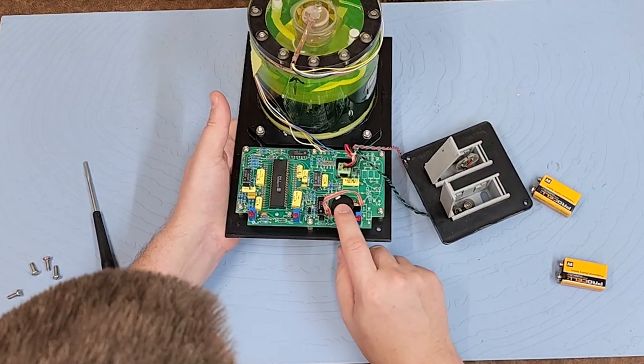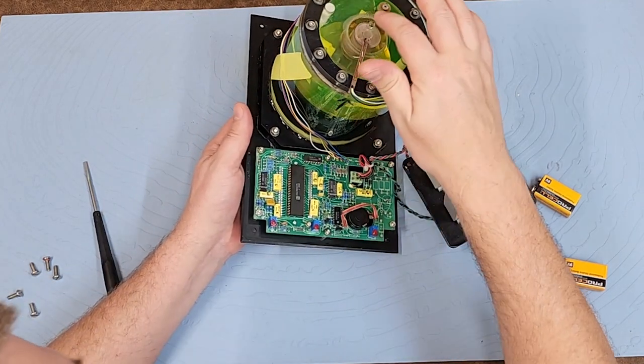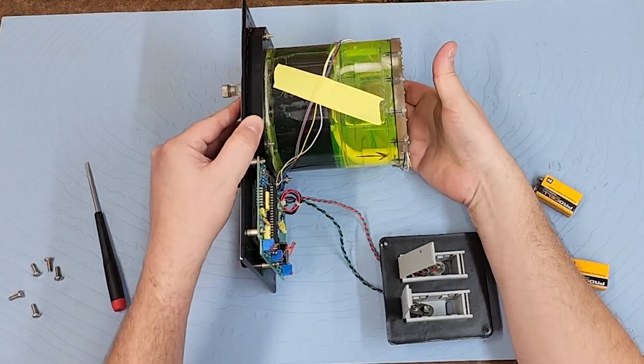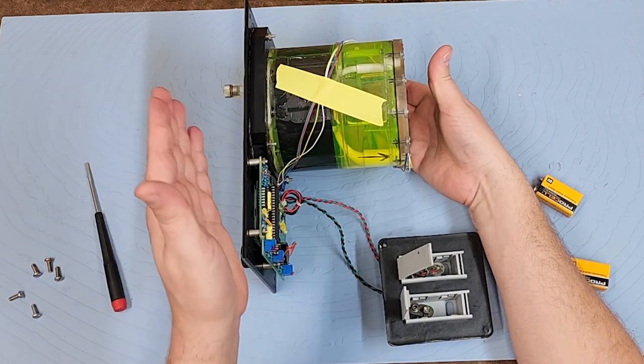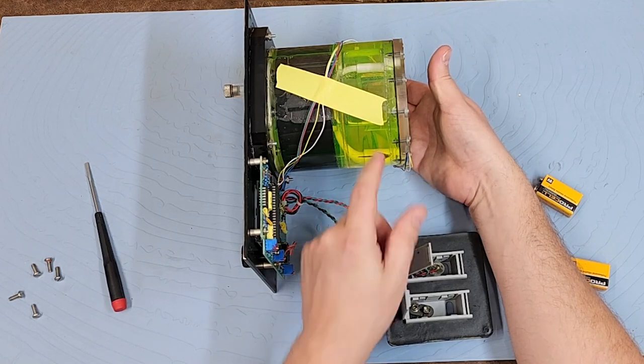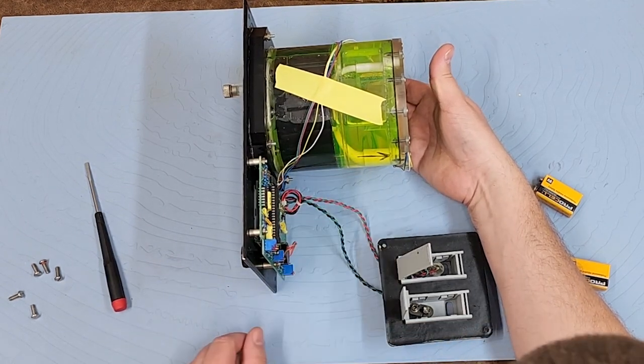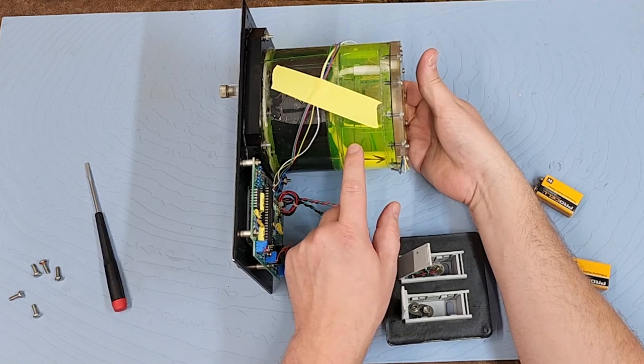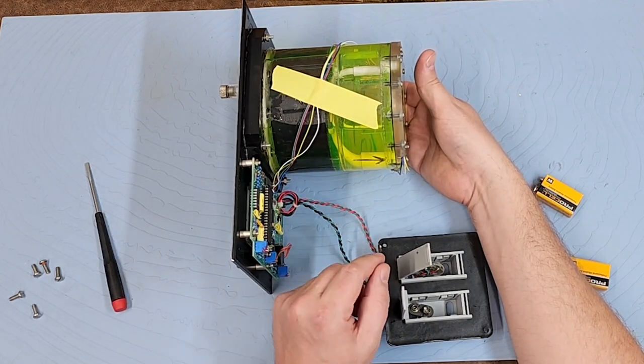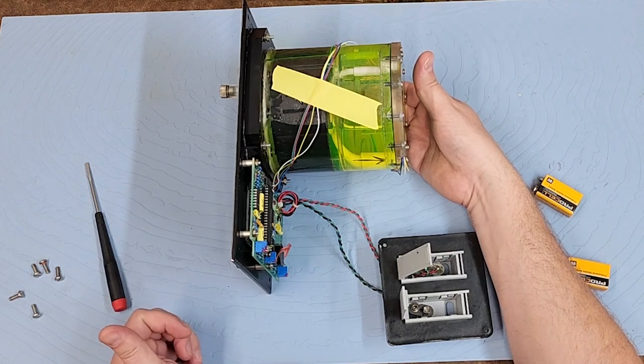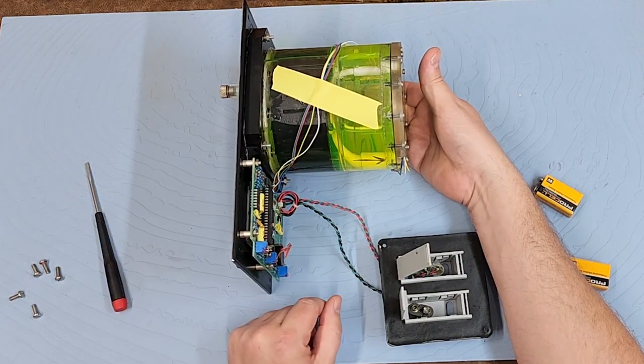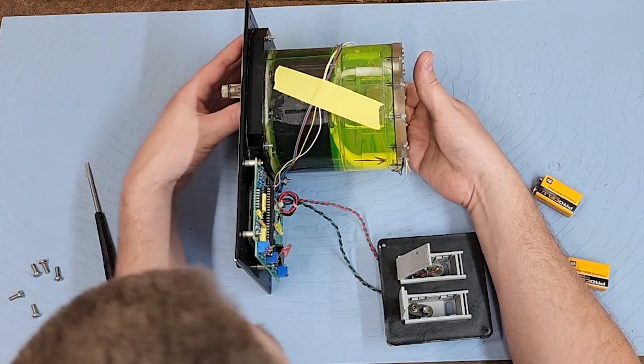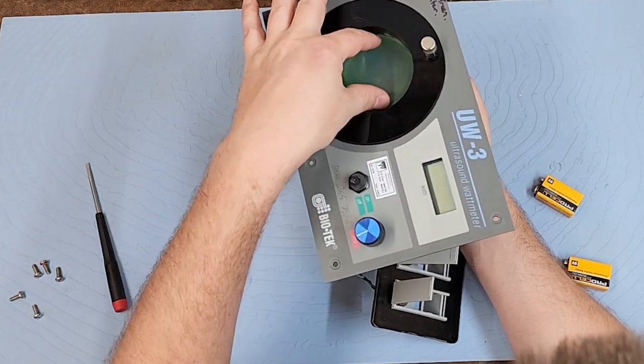And let's see, right here is my zeroing potentiometer, and you can see that I have a load cell in there. And just like I said, just like a scale, there is a load cell in there and it is going to press down on it with just wave energy, and that's how it forms a reading. Pretty cool stuff. So it clearly has some sort of ethylene glycol or antifreeze in the chamber right here. They do that because, A, it doesn't grow bacterial growth, and B, it doesn't corrode - it's a corrosion inhibitor. So two good reasons to use it.